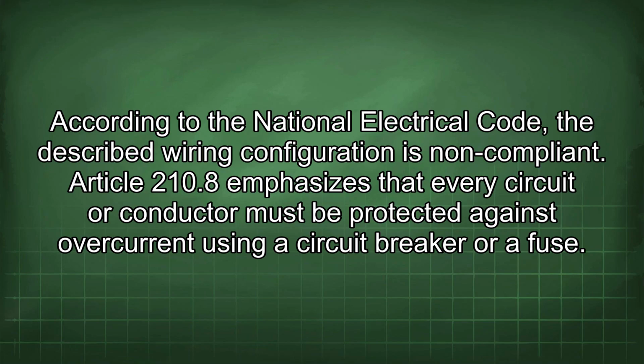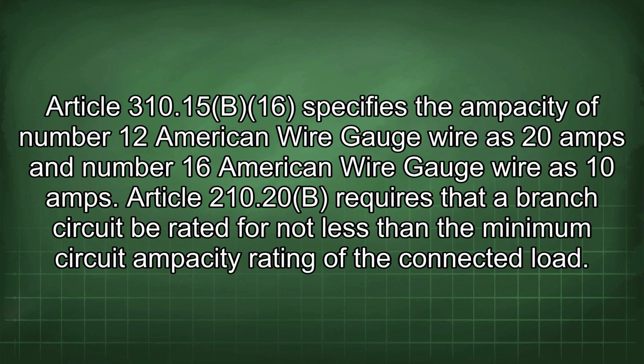According to the National Electrical Code, the described wiring configuration is non-compliant. Article 210.8 emphasizes that every circuit or conductor must be protected against overcurrent using a circuit breaker or a fuse. Article 310.15(B)(16) specifies the ampacity of number 12 American wire gauge wire as 20 amps and number 16 American wire gauge wire as 10 amps. Article 210.20(B) requires that a branch circuit be rated for not less than the minimum circuit ampacity rating of the connected load.